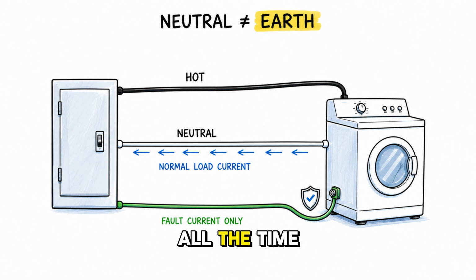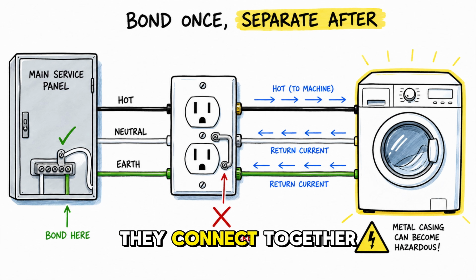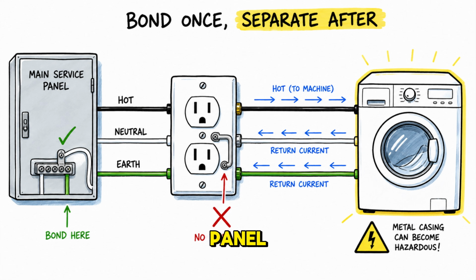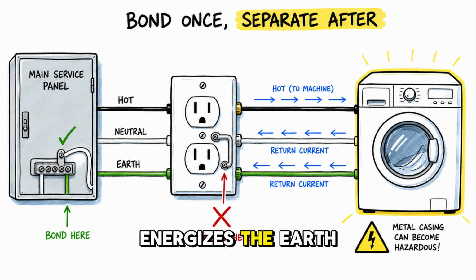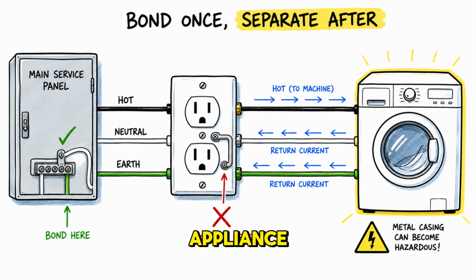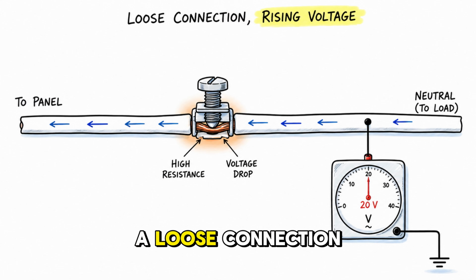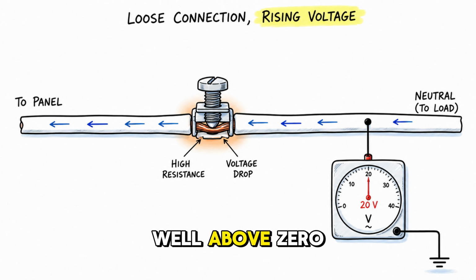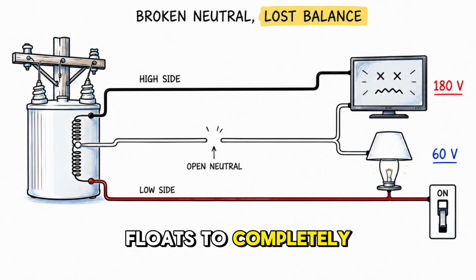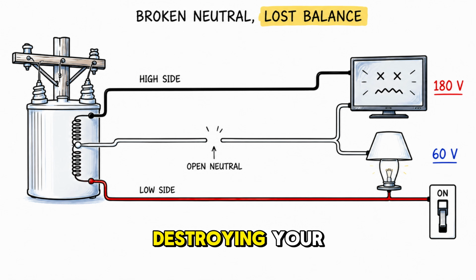Neutral carries current all the time. Earth carries current only during a dangerous fault. They connect together only at the main service panel. Connecting them anywhere else energizes the earth conductor, making every metal appliance casing in that circuit a severe shock hazard. The neutral wire is supposed to sit at 0 volts, but hidden faults can instantly make it lethal. A loose connection raises the neutral voltage well above zero through a resistance voltage drop. A broken neutral floats to completely unpredictable voltages, destroying your appliances without ever tripping a breaker.